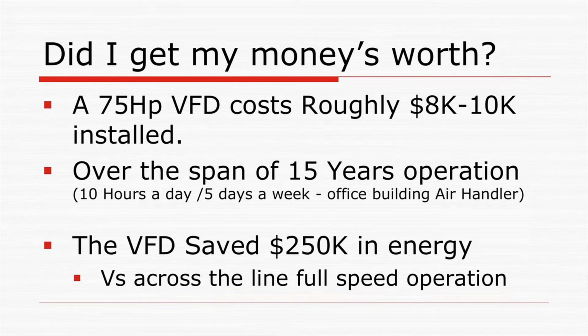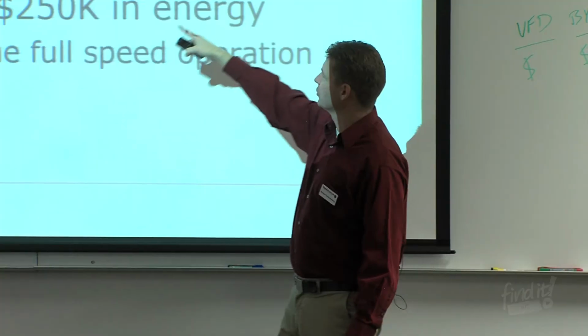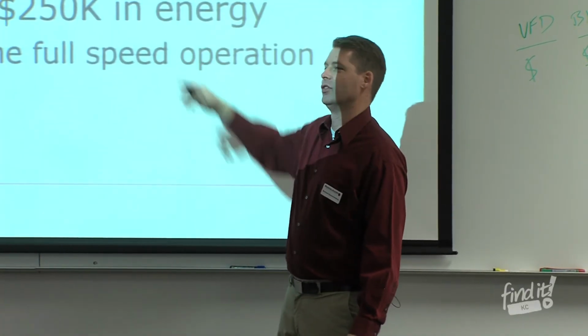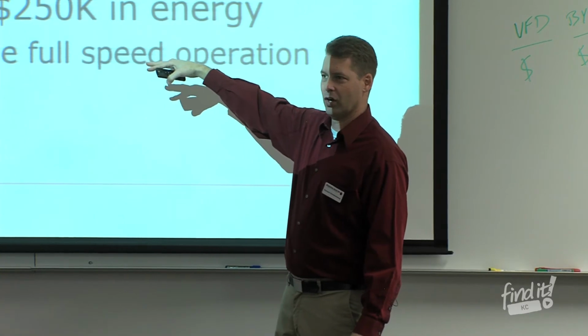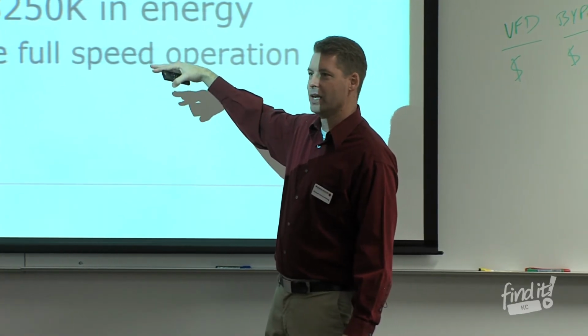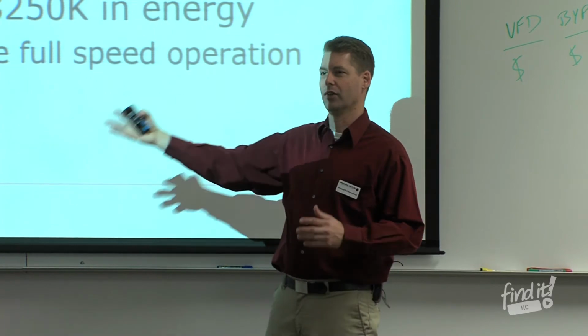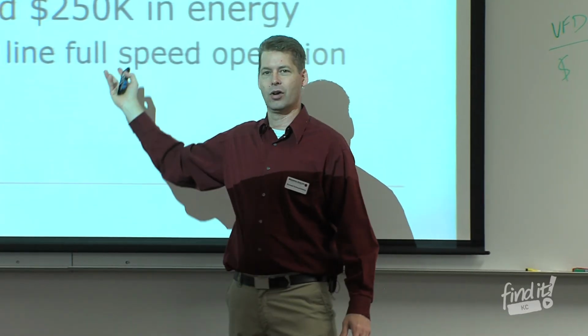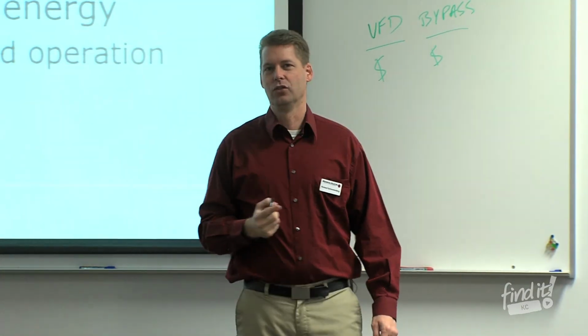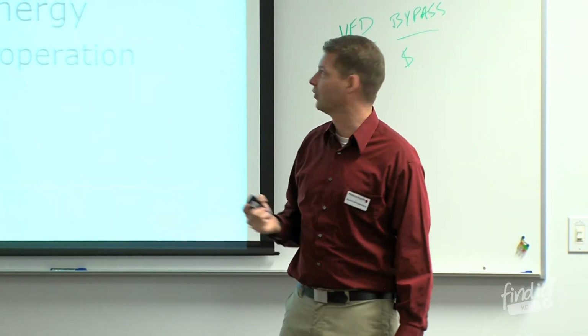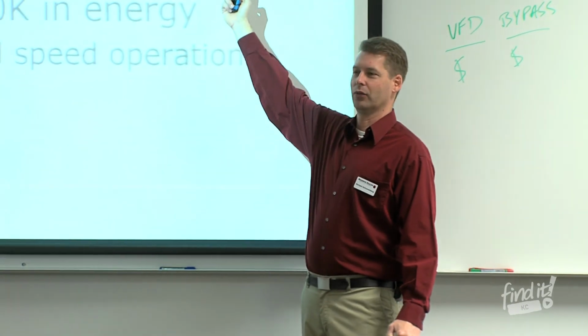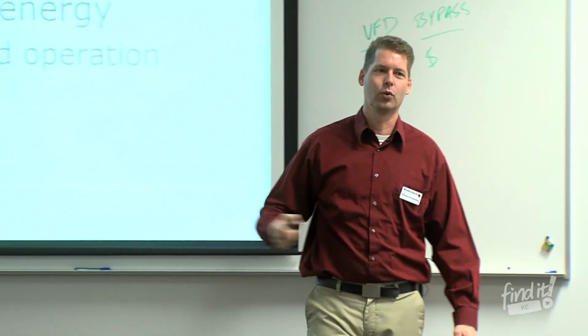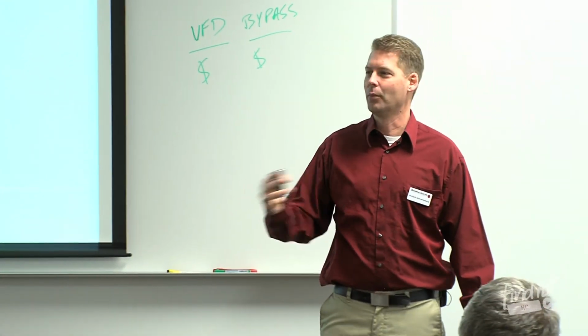about 8 to 10 grand. Well, over the span of 15 years, if we're using 15 years as its lifespan, and if we're being conservative, running only 10 hours a day, 5 days a week, because we're talking office building kind of stuff, how much did that energy savings cost you, and how much did it save you? Well, eventually I could have done the cost and given you the numbers of how much electricity is used, but if we'd have run that motor across the line compared to a VFD, the difference in cost there was $250,000. So in a way you could say the VFD has saved you $250,000 in the course of 15 years, and you could say thank you at the end of 15 years, buy another one for 10 grand and realize that every year you're going to save again another $25,000 or another $20,000 of electricity by having that VFD instead of not having it.